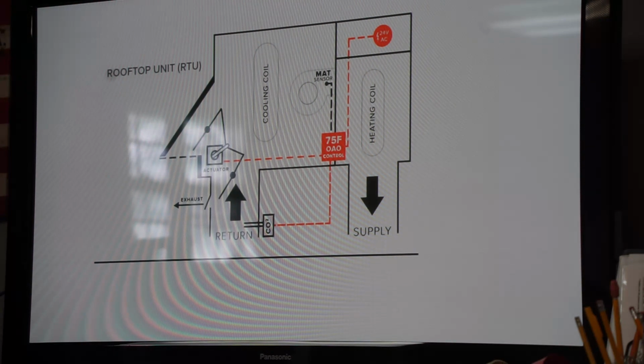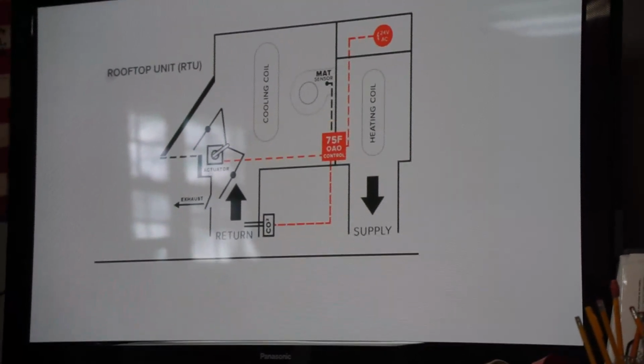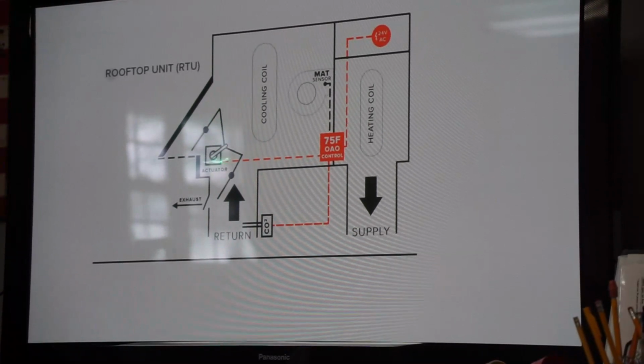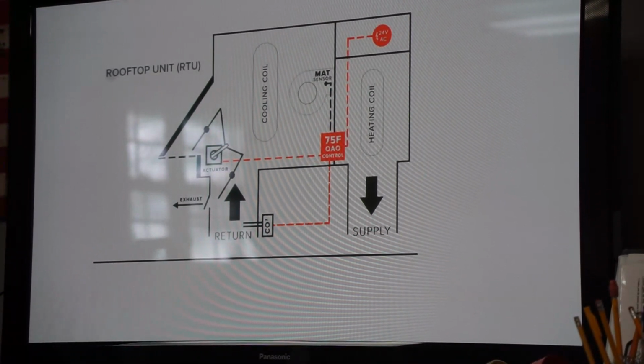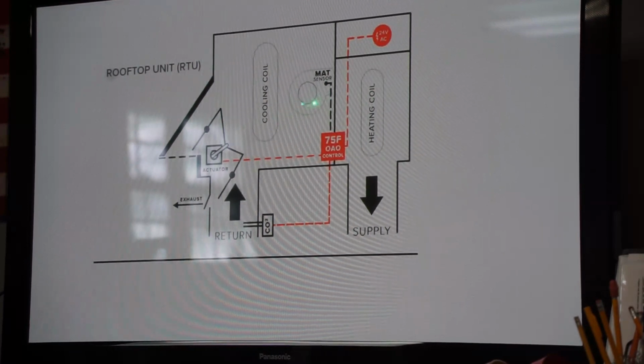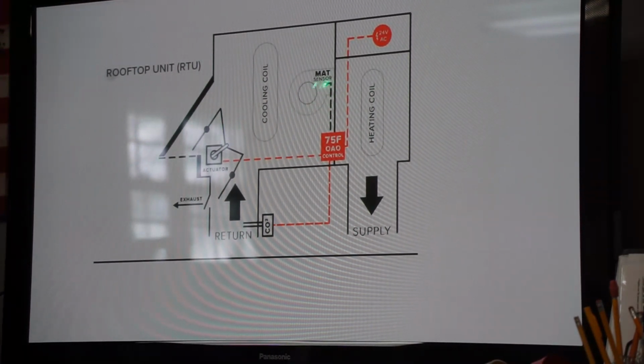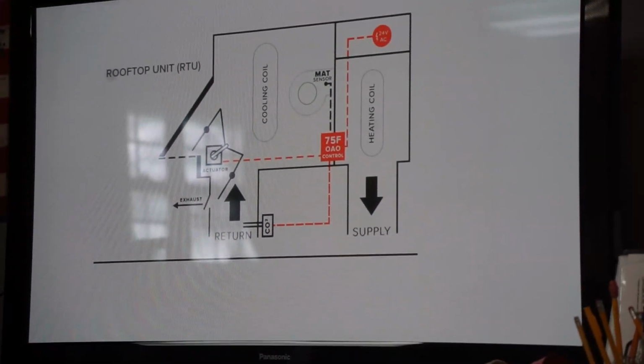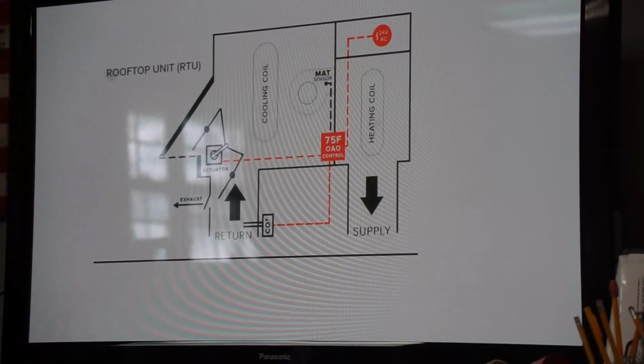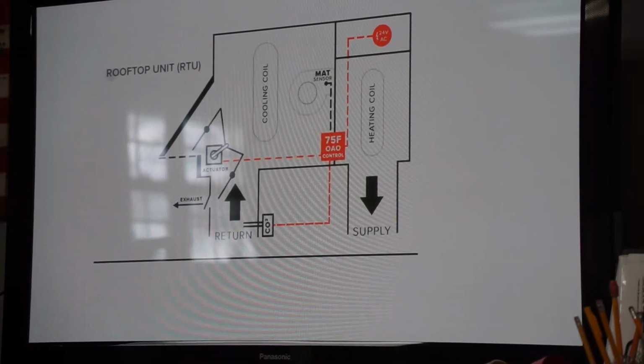And I don't put the sensor, this is the old school sensor back in the day, just a little thermistor on the end of it. This typically gets put in the blower section. And the reason is that in this area with those dampers, it's incredibly turbulent. There's a lot of attempted mixing going on, doesn't always happen, but we're never going to get a true mixed air temperature in that mixed air section. So don't be misled, but see how it says mixed air temperature sensor right there? That's downstream of the cooling coil. Well, it's not truly mixed air, but it plays well with the economizers, and we'll go over it.